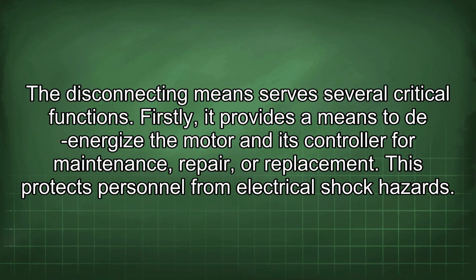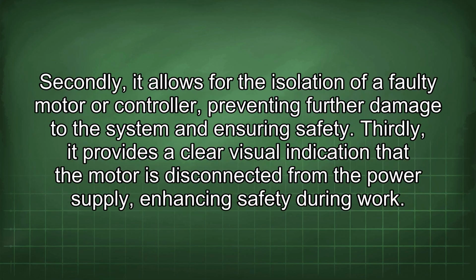The disconnecting means serves several critical functions. Firstly, it provides a means to de-energize the motor and its controller for maintenance, repair, or replacement. This protects personnel from electrical shock hazards. Secondly, it allows for the isolation of a faulty motor or controller, preventing further damage to the system and ensuring safety. Thirdly, it provides a clear visual indication that the motor is disconnected from the power supply, enhancing safety during work.